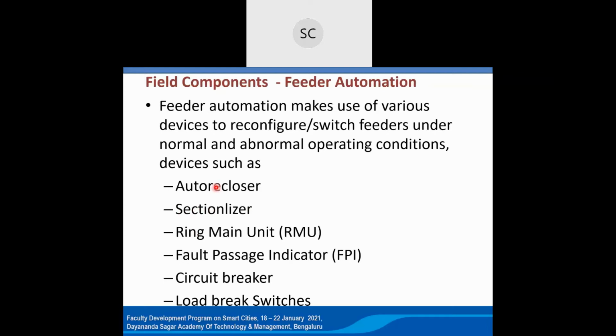And this will be one auto recloser, multiple sectionalizers. Generally, this is how we go about the design, based on the field survey. Maybe one auto recloser with 4-5 sectionalizers under it can come in the radial feeders, or however it happens. And again, we use ring main units. Ring main units come in 3-way, 5-way, 7-way, and multiples.